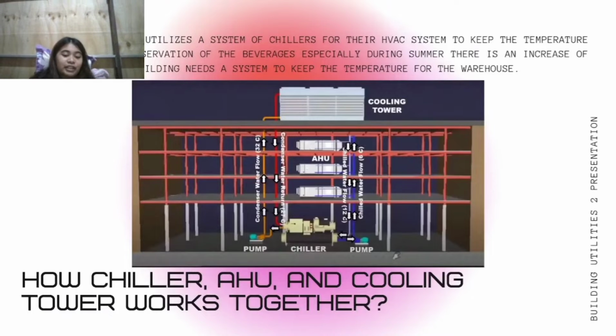So how do a chiller, AHU, and cooling tower work together? The HVAC system in the wine warehouse mainly utilizes a system of chillers. Since the warehouse is concerned with wine, craft beers, and artisan spirit inventory, a certain temperature should be kept to keep the quality of the drinks. Thus, a system of chillers is being utilized in the warehouse. This system has the following components that work together to keep the warehouse's temperature low: a chiller, a cooling tower, a pump, and an air handling unit.